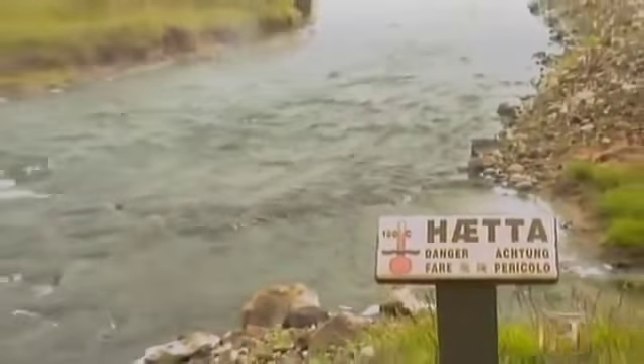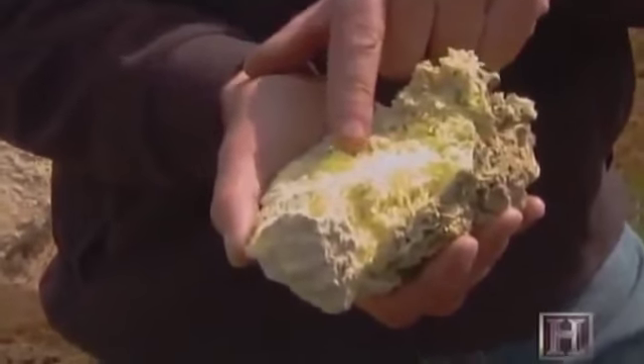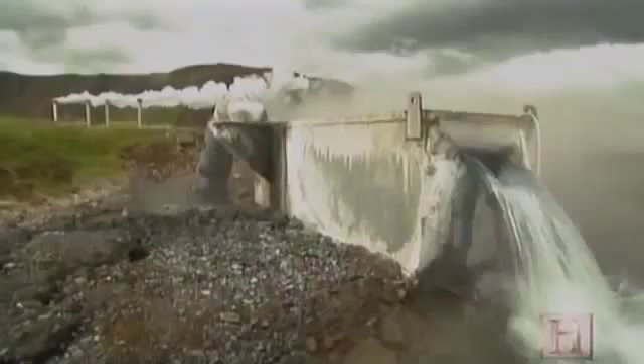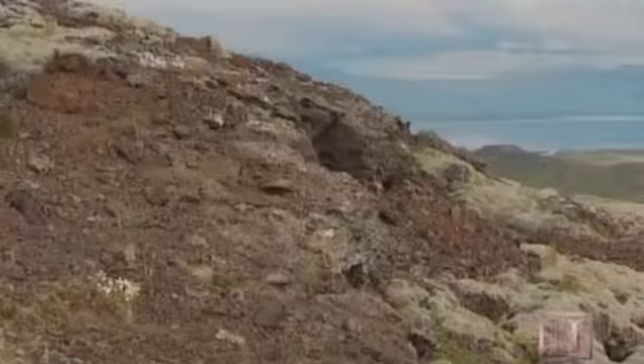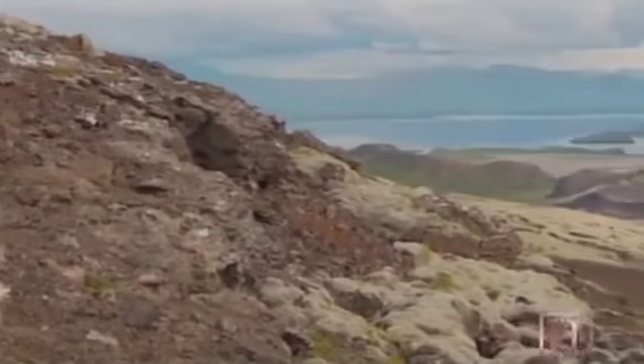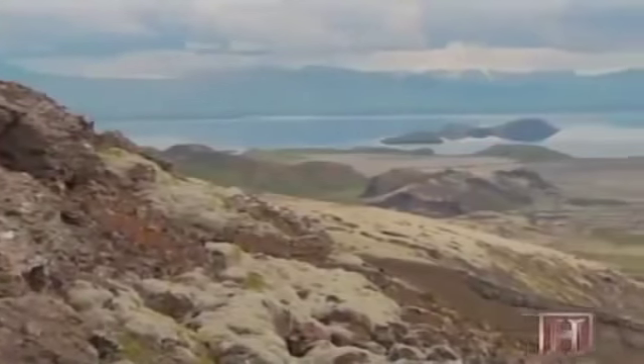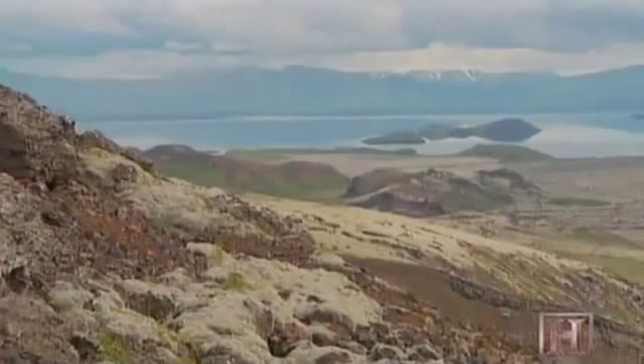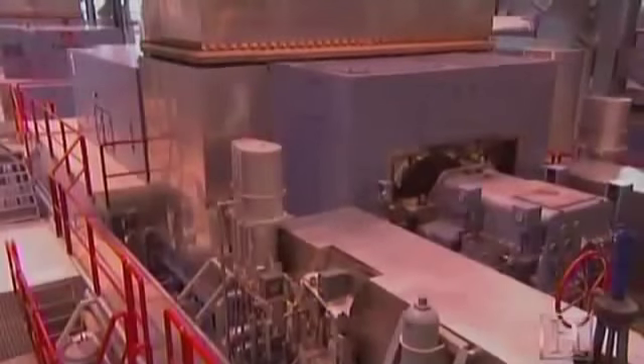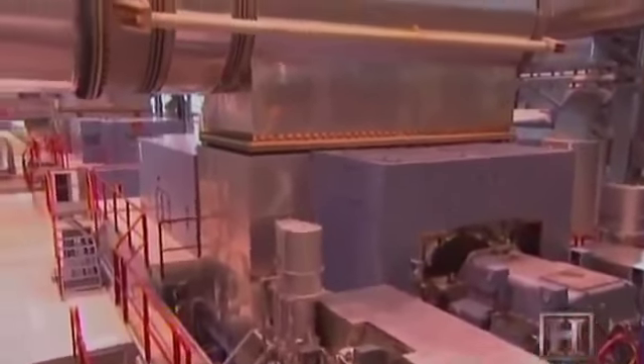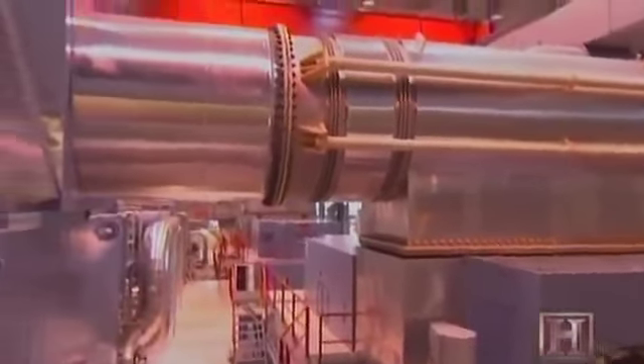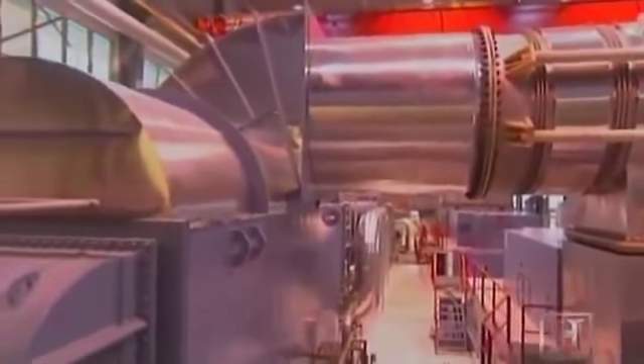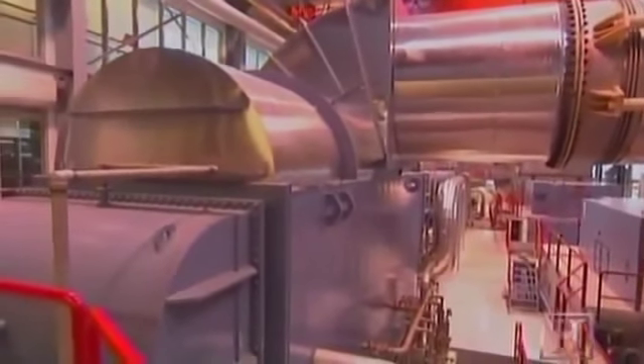Nesjavellir is a high-temperature geothermal zone, meaning the water below the surface is hot enough to dissolve sulfur and other corrosive minerals. For this reason, it can't be used directly in the population's heating system. Instead, the power plant uses the geothermal water to heat cold fresh water pumped in from a nearby aquifer. In the first stage of heating the water, excess steam from the electricity-producing turbines is used to bring the cold water up to 125 degrees.